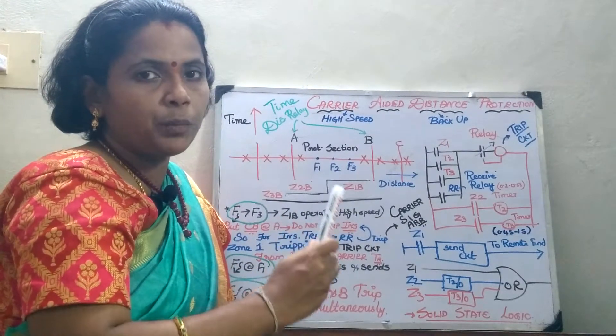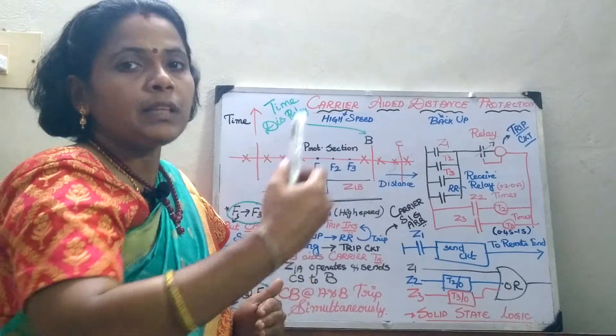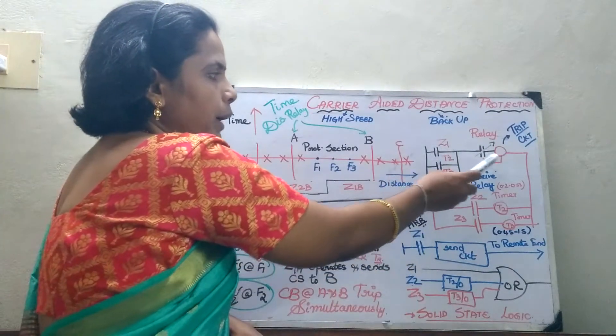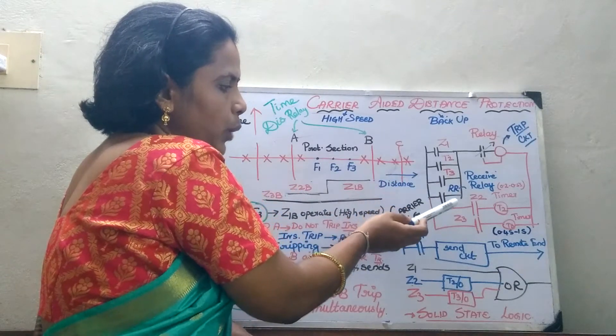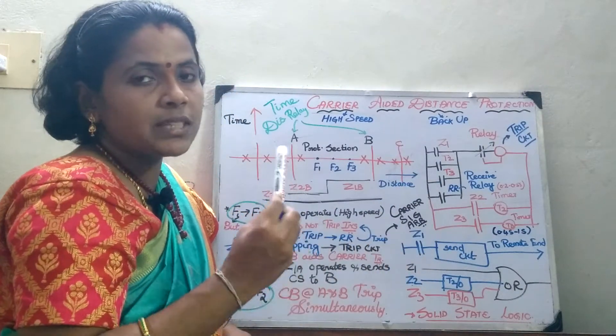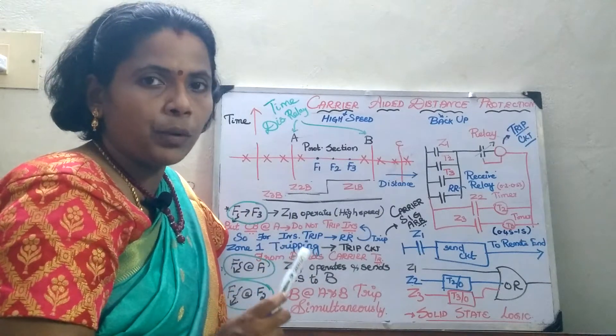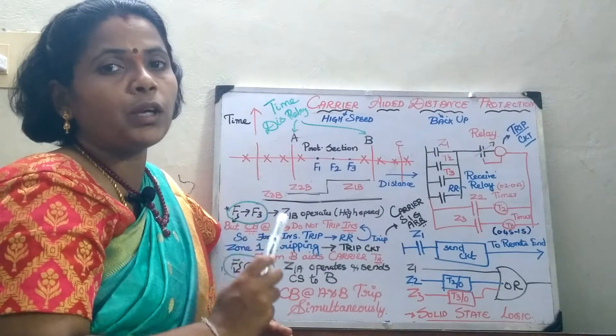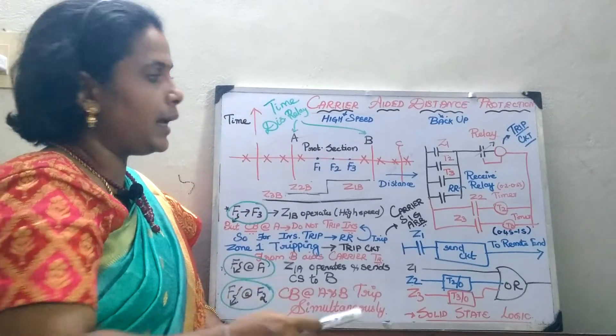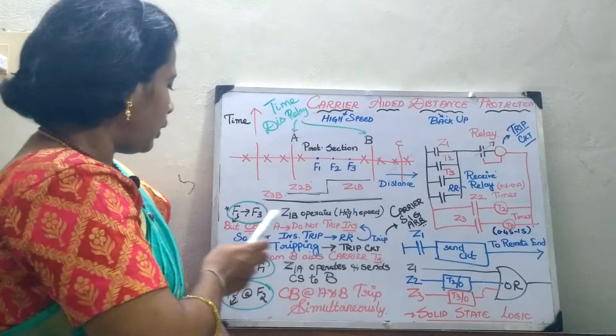Usually the first zone protects 80 to 90 percent of the line, the second zone protects the remaining part of the first zone and 50 percent of the adjacent line, and Z3 is used as backup protection. Z1 will operate immediately and trip the circuit, whereas after a time delay T2 and T3, Z2 and Z3 will work. A receive relay is used to send the carrier signal either from A to B or from B to A, to aid the simultaneous opening of circuit breakers at both ends — which is not achieved by distance relay alone.